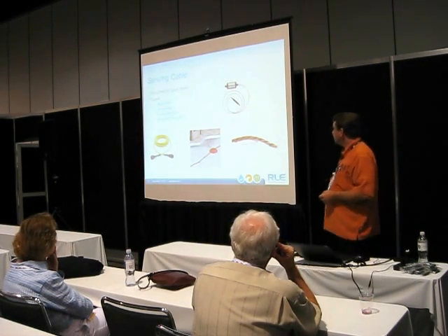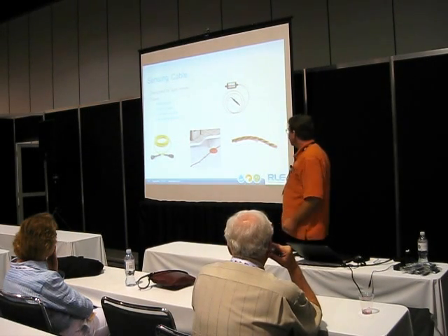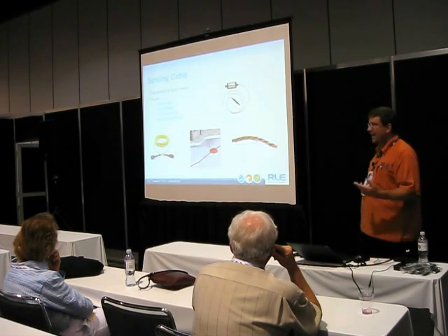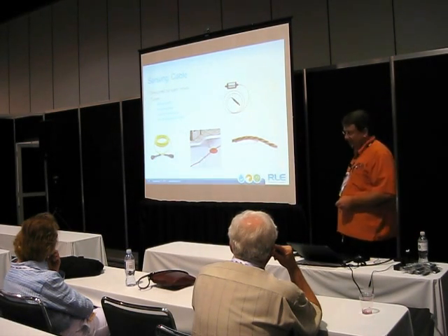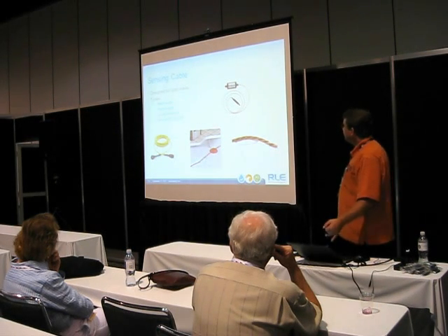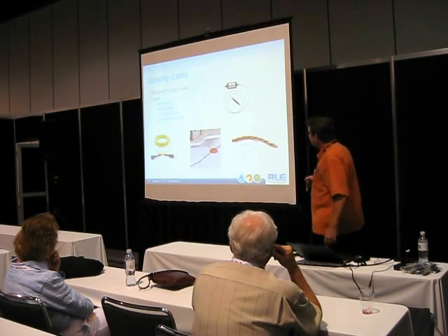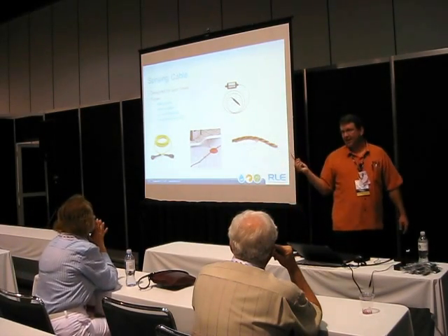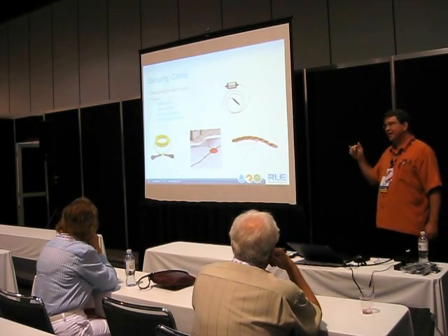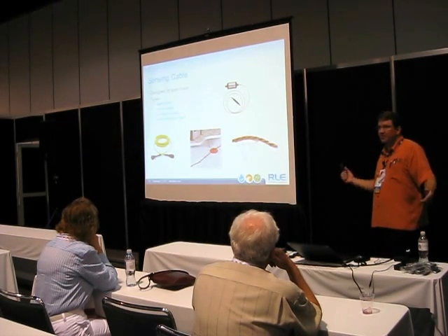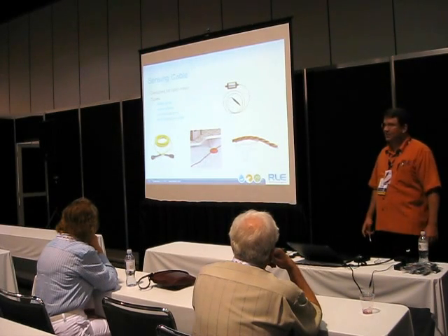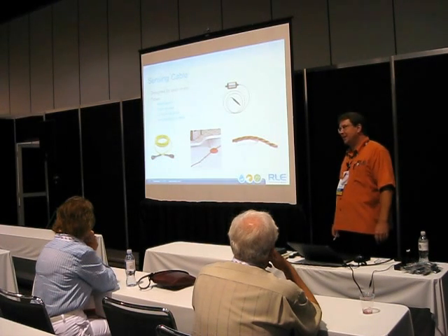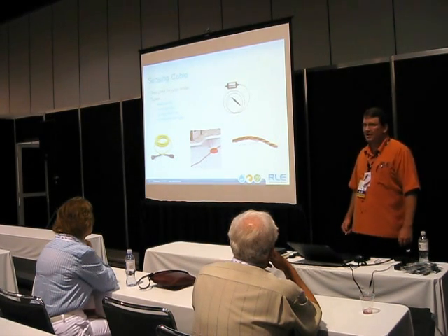We also have point sensors. Some systems may claim to be a leak detection cable, but it's literally a series of spot detectors along the length of the cable. Again, not going to be quite as reliable as a true cable-based solution. And then another type of leak detection cable: when you look at the cable, you have sensor wires running parallel, but some cables will actually have a conductive jacket on those sensing wires. The problem with that is dirt or dust landing on that jacket. Over time, it will eventually bridge those two sensing wires and result in false alarms and nuisance alarms. And I know people turning off the systems because they get tired of those. Suddenly you think you have leak detection, but somebody turned it off just to quiet the system. You don't have leak detection.